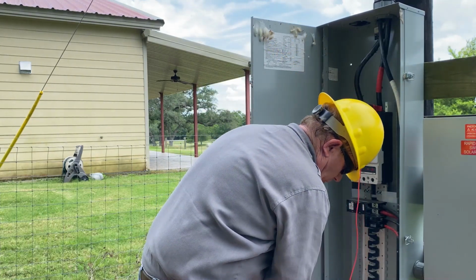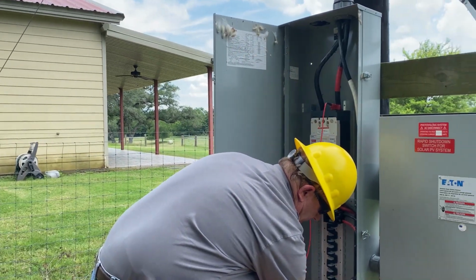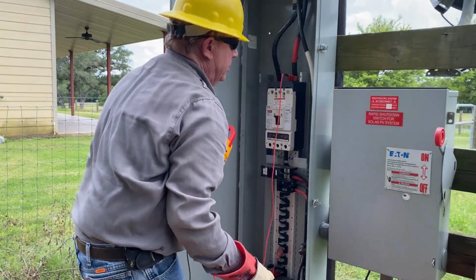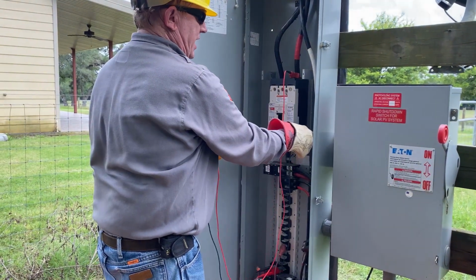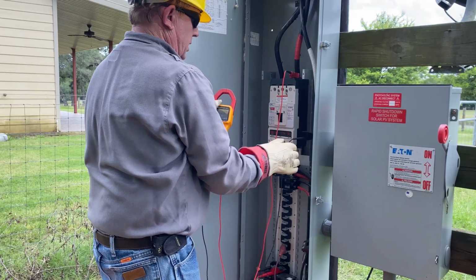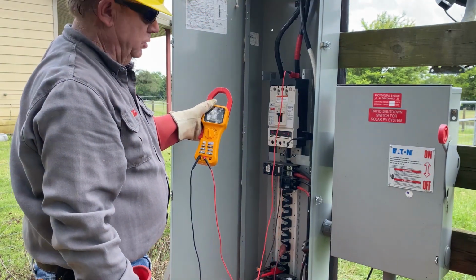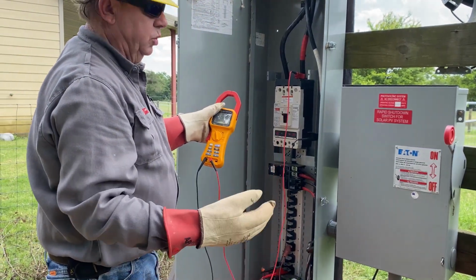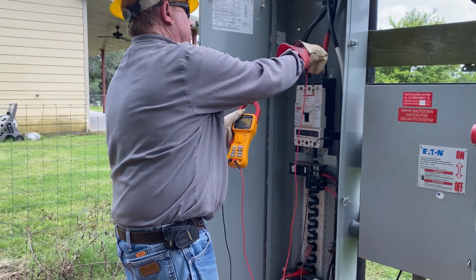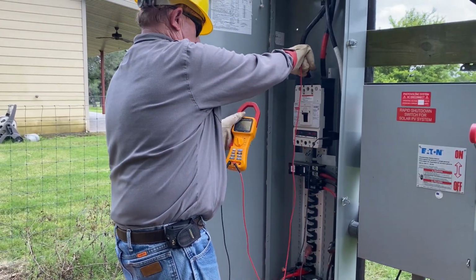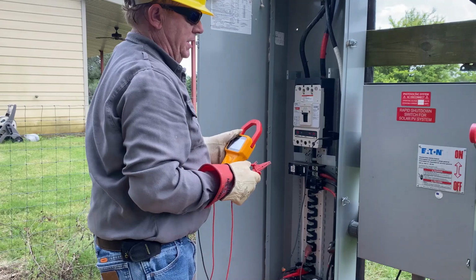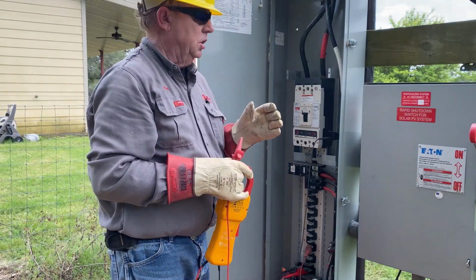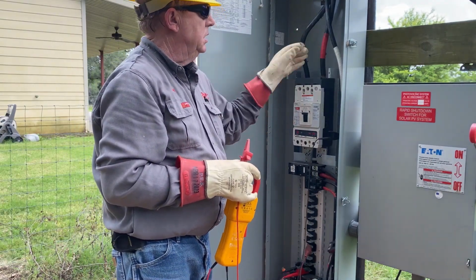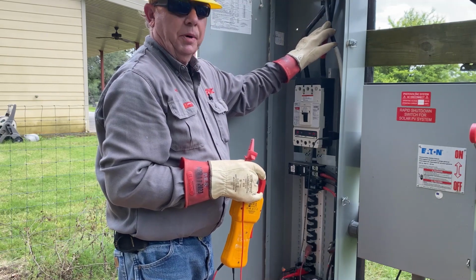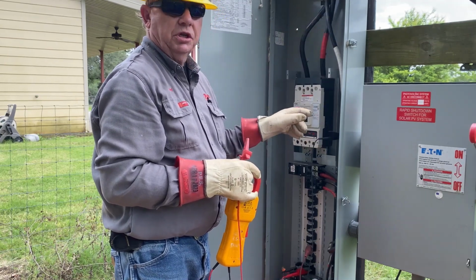I'm going to take the voltmeter lead from the neutral bus bar down here, and I'm going to move it up here to where he thinks his neutral is, and that balances the voltage. So now I'm 122.8 and 122.8. Now, all the loads that are causing neutral unbalance are all tied to this jumper and this connector that's bolted to the sheet metal.